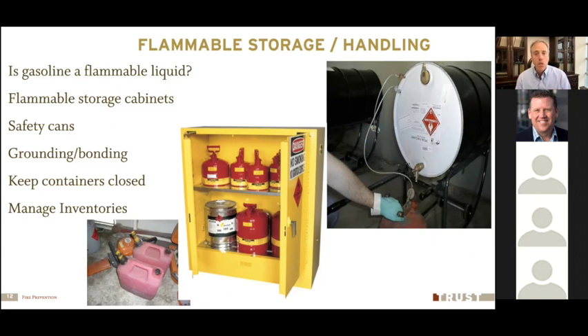Gasoline is definitely below that temperature. In fact, gasoline's flash point, the temperature where its vapors can be ignited, is something like minus 45 degrees. And so if we have those flammable materials that we're using or keeping, we need to make sure that those are stored properly. Gasoline, for example, should be stored in a metal safety can. And if we have these inside of a building that we're occupying, then those should also be stored inside a flammables cabinet, as should other flammables if you have large quantities of those materials in your facility.